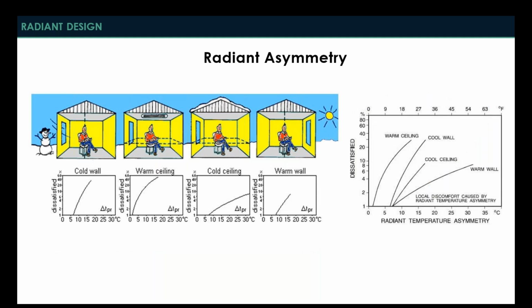Another aspect that's unique to radiant design is what is known as radiant asymmetry. This is really how people react to surface temperatures that are around them. This isn't something that maybe we look at enough, and on all-air systems we hardly look at it at all, because we're less concerned with the temperatures of these various surfaces. But when we're doing a radiant system, you really have to be concerned about walls, ceilings, floors. Are they warm? Are they cold? Because if they're too warm or too cold, that's going to have a very negative impact on occupant comfort. There are design parameters that show what the temperature delta can be for these various surfaces before someone is going to think that they're uncomfortable. And we'll get a little bit more into that in a minute in terms of what these surface temperatures really want to be for various radiant system types.